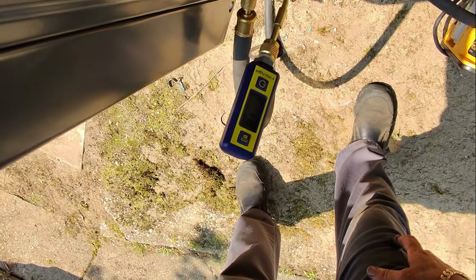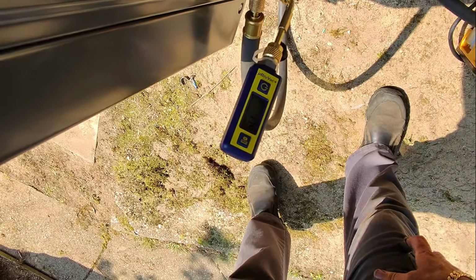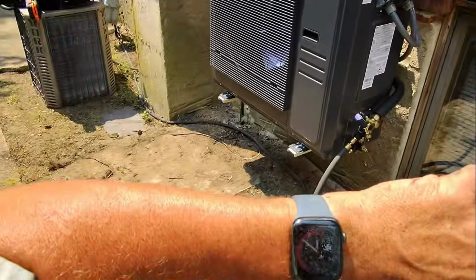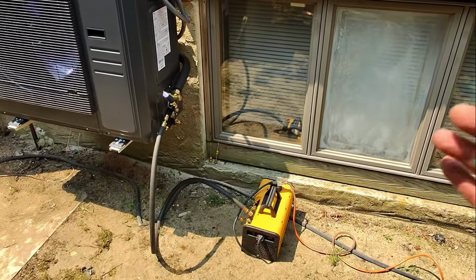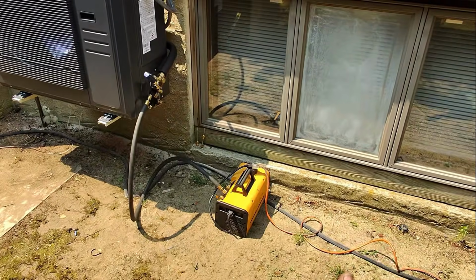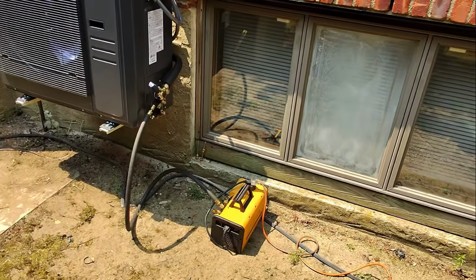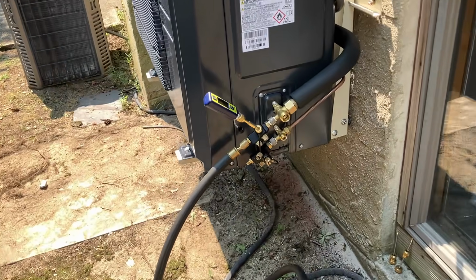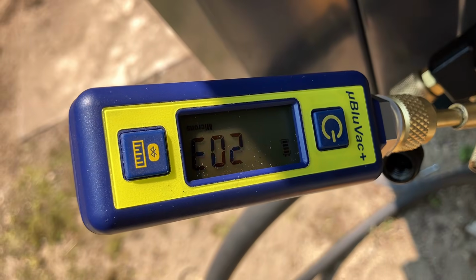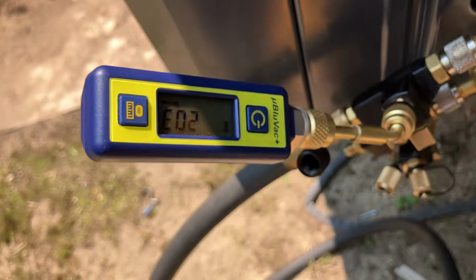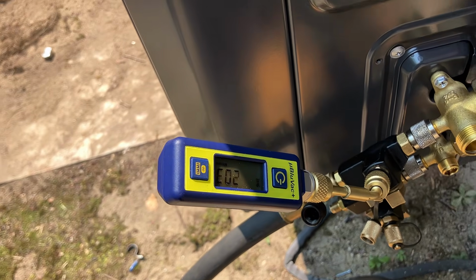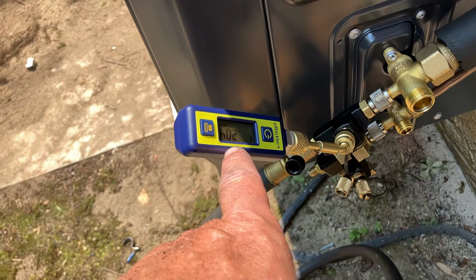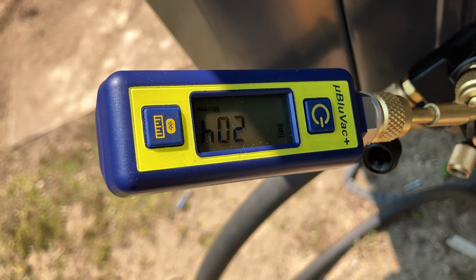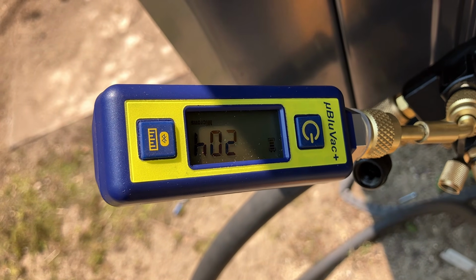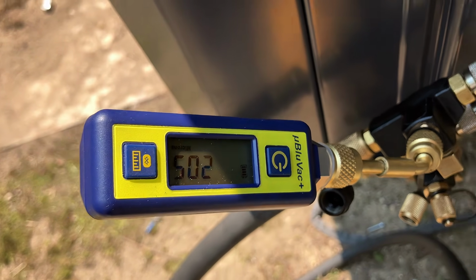127. 177, 178, 180. 9 minutes to 12. So this process we've been working on, the vacuuming and pressure test, almost an hour. Not too shabby. 203. Literally the valve's been closed for several minutes. So it's jumping between 204 and 203. Or it's calling me a liar now.